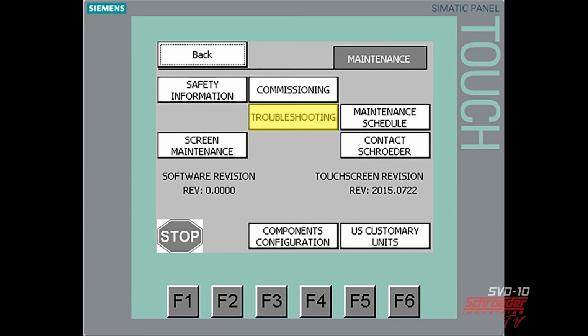Troubleshooting provides information regarding basic problems encountered while operating the SVD. On these screens, the user can find the cause and remedy of the problem by locating the error message. Maintenance schedule provides the user the schedule that needs to be followed to ensure correct maintenance. There are inspection and maintenance schedules in the following categories: general, fluid filter, electrical, vacuum pump, functional test, and drain pump charge pump.